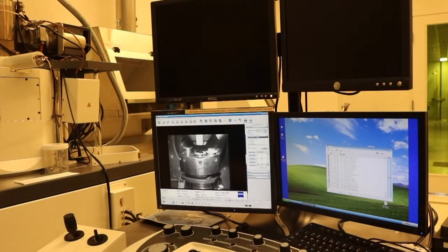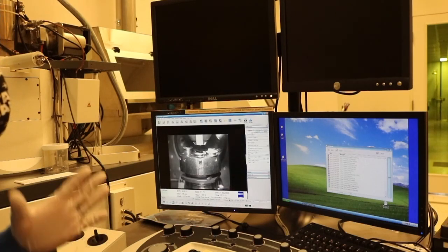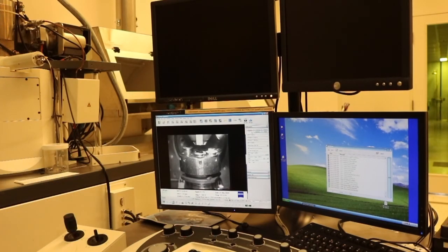And for things where you're doing standard imaging, you'd pick a smaller one. Today, we'll start off with the 30 micron. So we're going to start off at 5 kilovolts and a 30 micron aperture. Typically, current-wise, that's probably around 250 picoamps. If your sample is very beam-sensitive, you might consider using less current.